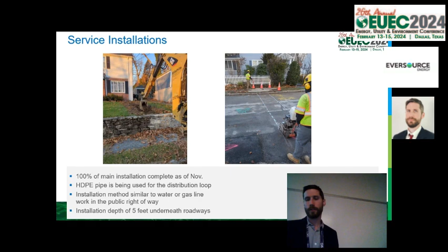It's a little bit deeper than traditional gas work. We're down at 5 feet in this case instead of 3, mostly for protection of the system and thermal performance. If you get too shallow, the frost line in Massachusetts is about 36 inches, and you'll start seeing degradation in performance because you're losing too much heat to the ambient atmosphere.